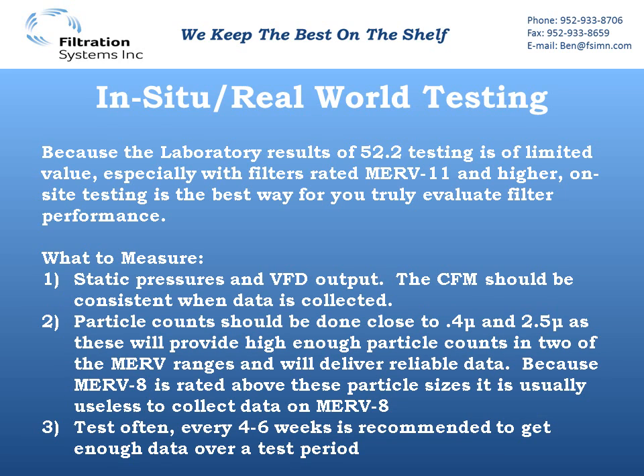For particle counts, we want to focus on the smaller sizes because that's what's in ambient air — usually around the 0.3 to 0.4 micron size, and then again around 2.5 to 3 microns. These will provide enough particle counts to deliver reliable data. MERV-8 filters are rated above these particle sizes, and the particle sizes that MERV-8 is designed to capture aren't statistically significant in ambient or outdoor air, making it very difficult to test reliably in situ because there aren't enough particles to give reliable data.